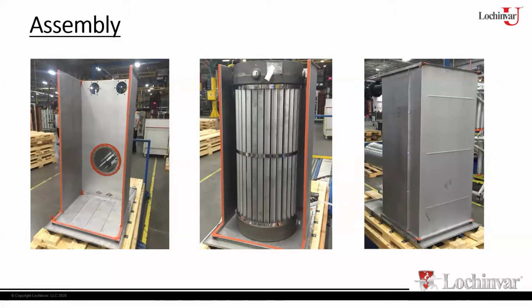If there is a leak in any of the seams from the combustion chamber side, well, you've got to think about this. When the heater is in actual operation and you're generating flue gases, I don't want those flue gases escaping through those gaps into the unit itself. If those flue gases get into the heater, then that's going to start affecting your electronics, right? Your blowers, your boards, your wiring. It's going to start affecting these different components, which can lead to operational issues. So we want to make sure everything is sealed airtight at that point. Now, once it's passed that test, we've got our sealed box. Now we can start adding everything else to it. So now we start adding all the other components.